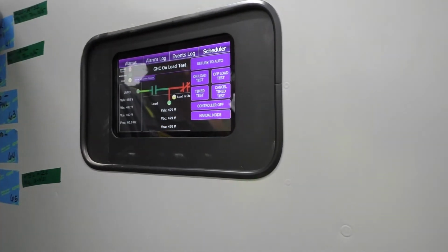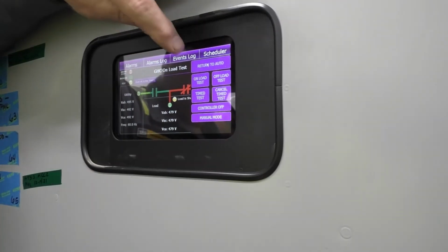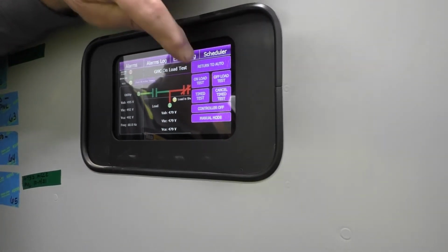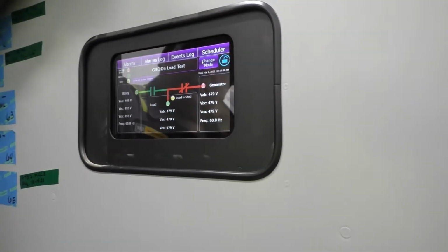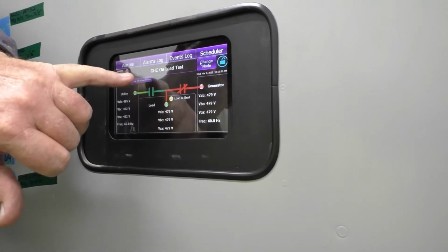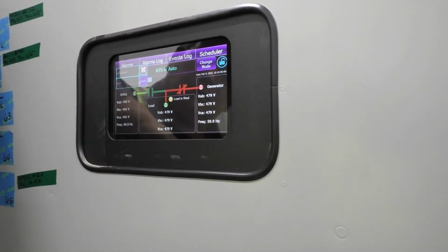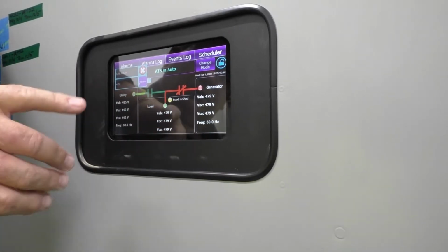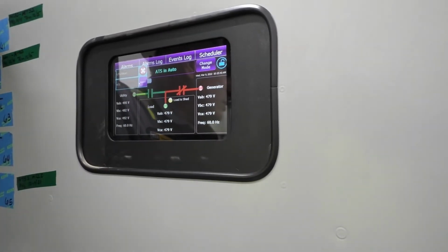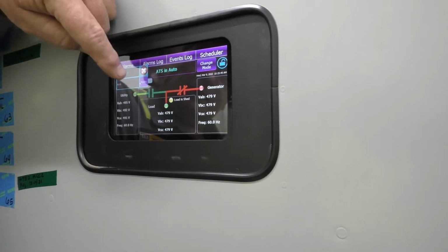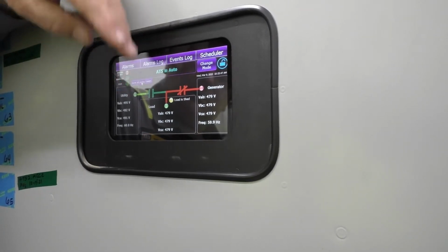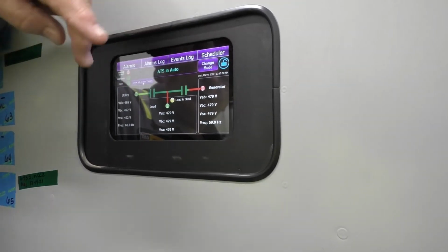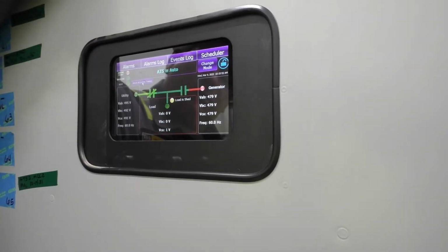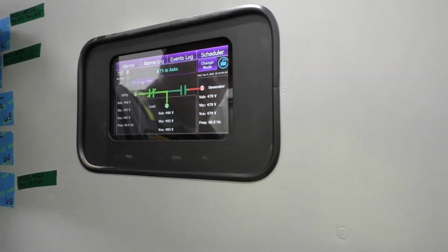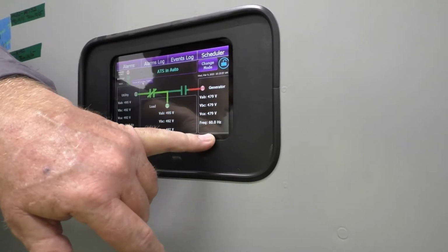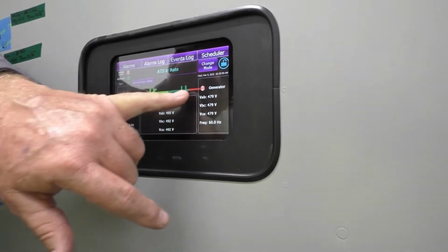Now when you get done wanting to do a manual test like this, you have to hit return to auto. Then it'll start a timer. And if you want to see the timers, touch the show active timers. It has a 5-minute return to utility. Usually it's set 10 minutes minimum, but we can bypass that. So now it opened the gen breaker, and it should close that one. We're back on utility. Now we're in cool down mode. You still see voltage because the generator's still running. You got voltage here, and it shows you which source you're connected to.